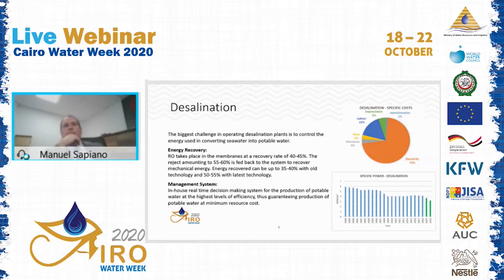And I have to say that there have been a lot of investments in energy efficiency in Malta. We have managed to reduce the energy required for the provision of desalinated water significantly. We are now reaching a requirement of around 3.8 kilowatt hours per cubic meter. Going back 10, 15 years ago, this was in the region of 7.